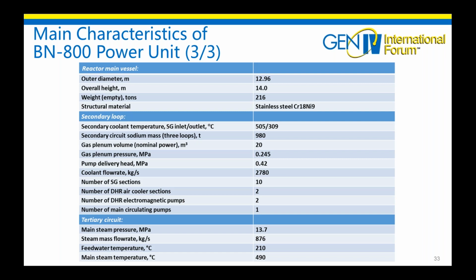So the temperature of sodium in steam generator inlet is 505 degrees and outlet 309 degrees. We have 2 decay heat removal air cooling sections, and we have a decay heat removal system in each loop. In BN-600 we have 8 steam generator sections. In BN-800 we have 10 steam generator sections in each loop. We call all these 10 sections like one steam generator. So we don't call that the steam generator is only one model.